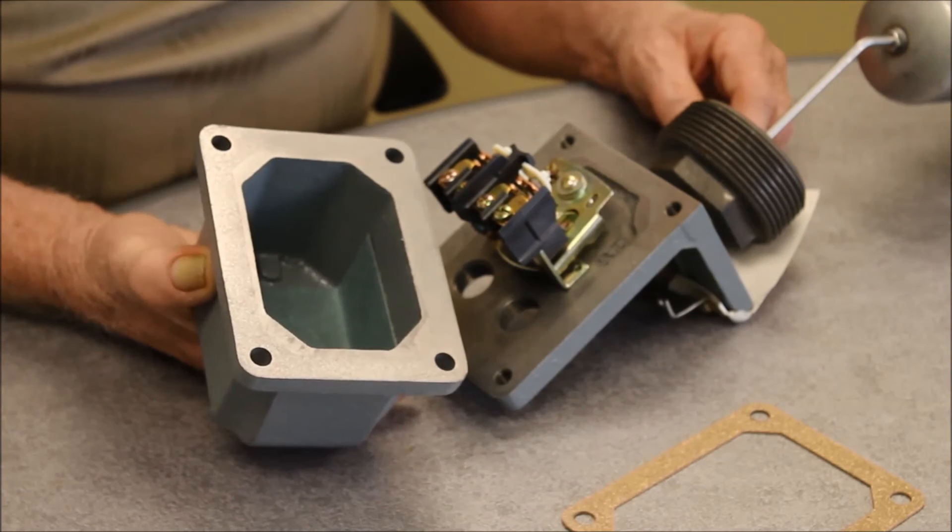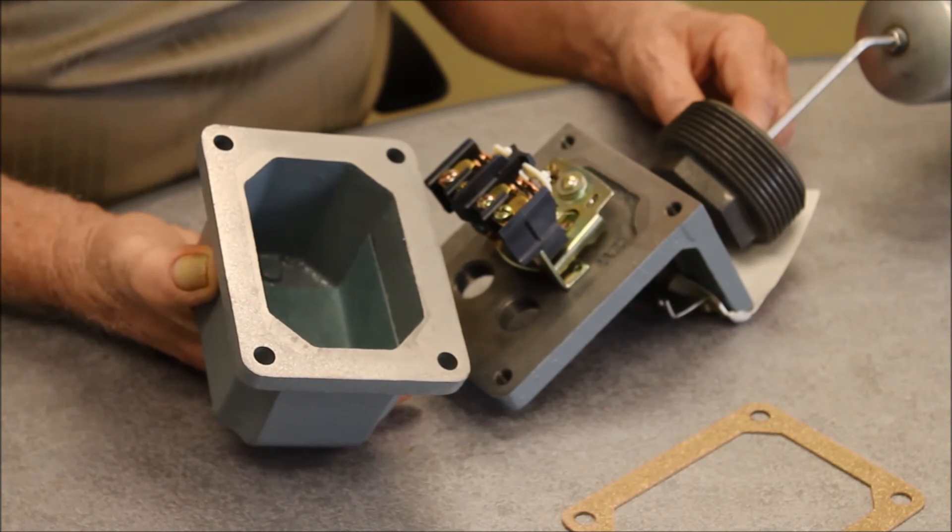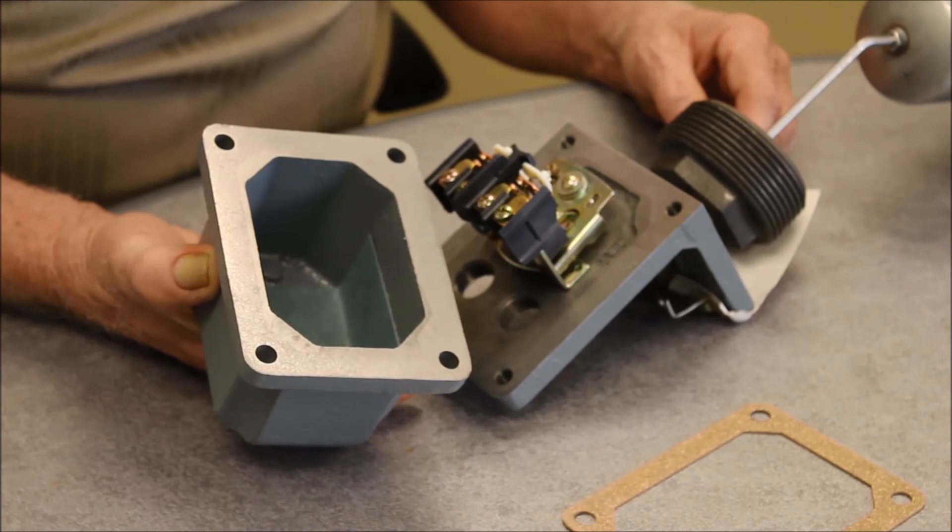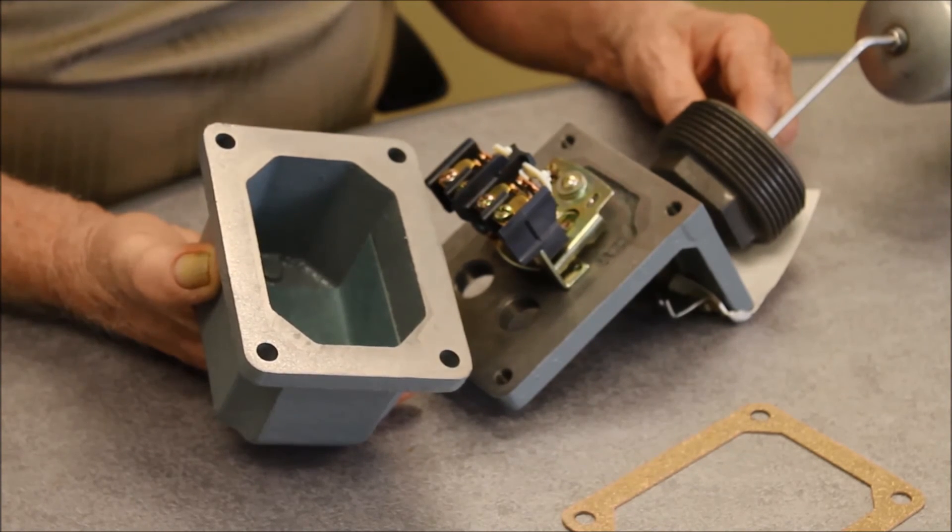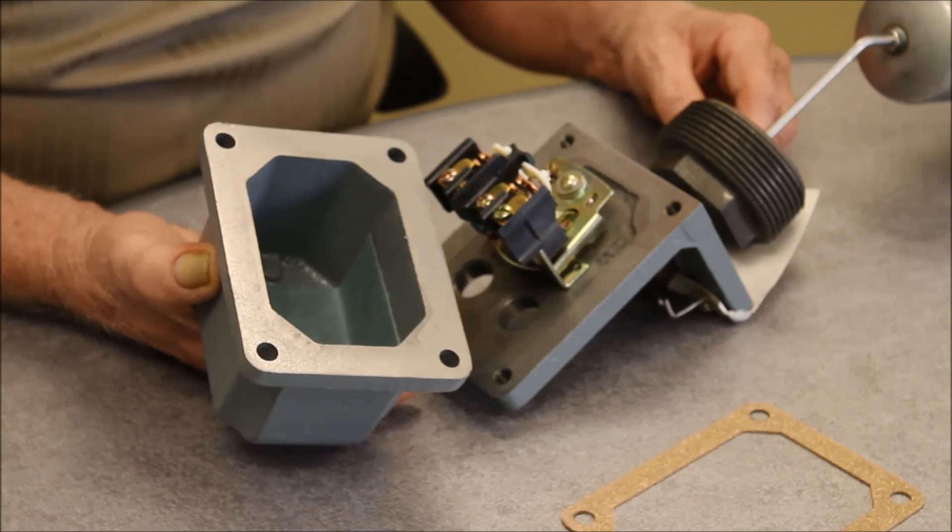The NEMA 7 and 9 devices for this reason are suitable for a high pressure wash down and may develop condensation inside the enclosure. This is normal for this type of device.